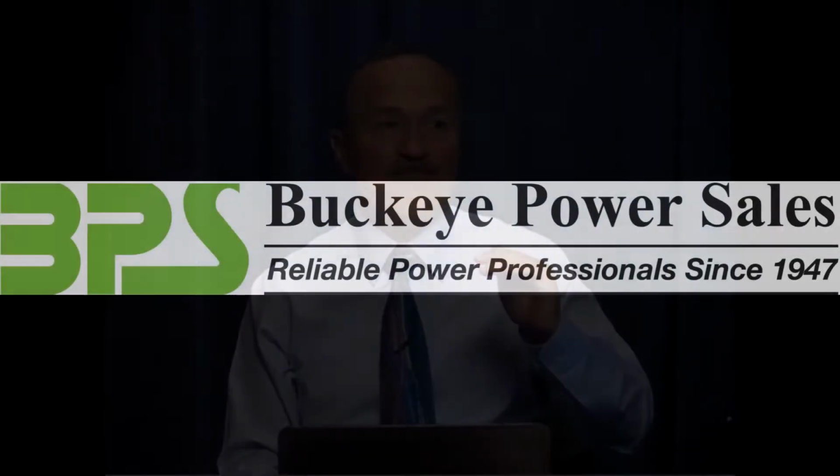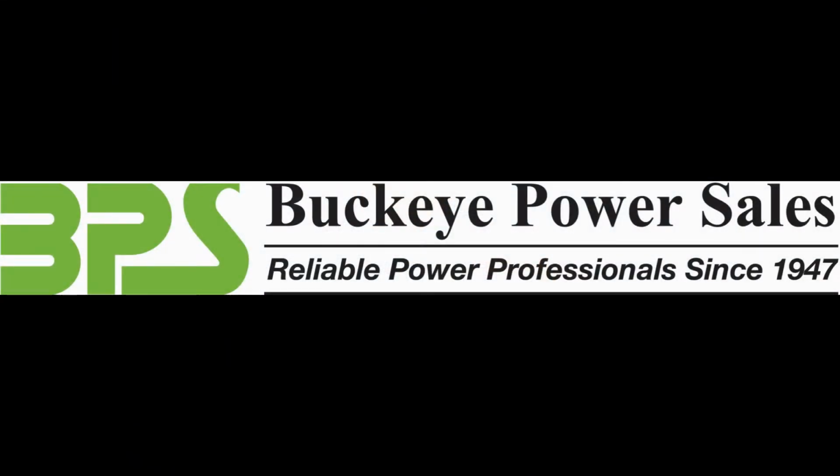What happened was when the World Trade Center went down, had all the fires, I think they ran fire hoses in there probably for 6 months, trying to stop the smoldering. It filled up the first 3 floors of the basement of the WorldCom, and that's where they had the emergency generators. New York has gone ahead and changed the code as to location of an emergency power supply system, so always check local codes during the early design phase.